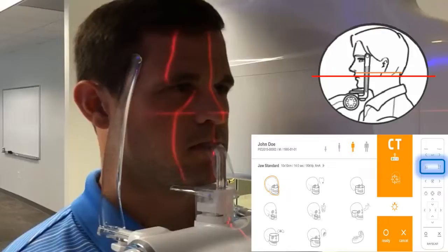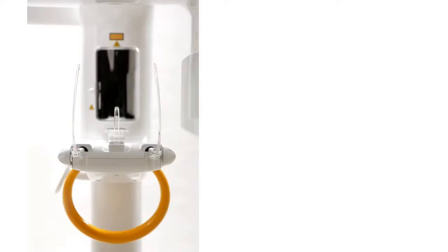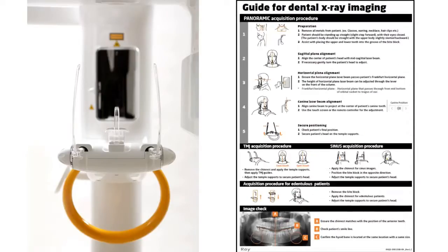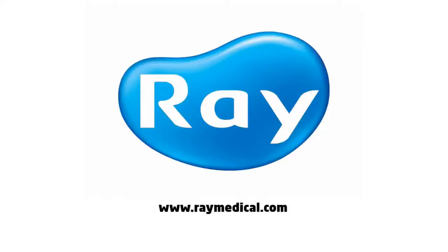Ask the patient to close their eyes to help them remain still for the duration of the exposure. Ask the patient to swallow and remain still for the duration of the scan. Move at least seven feet away from the unit and protect yourself from radiation. Press and hold down the exposure button for the duration of the exposure. For more information on proper positioning and usage of the Rayscan Alpha Plus, please consult the positioning guide. Thank you for watching.